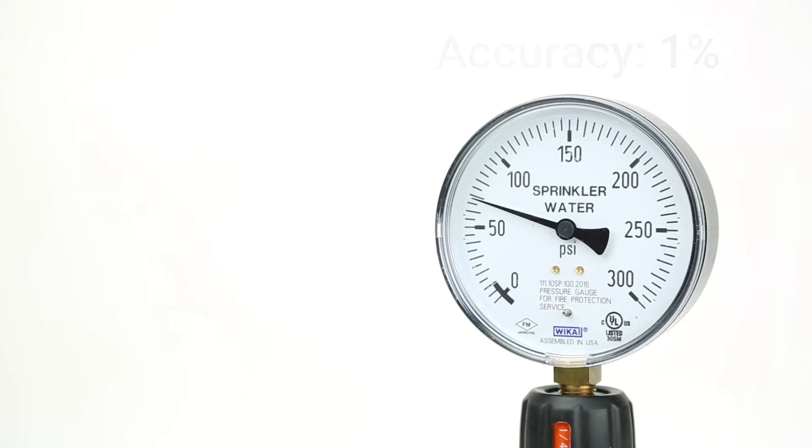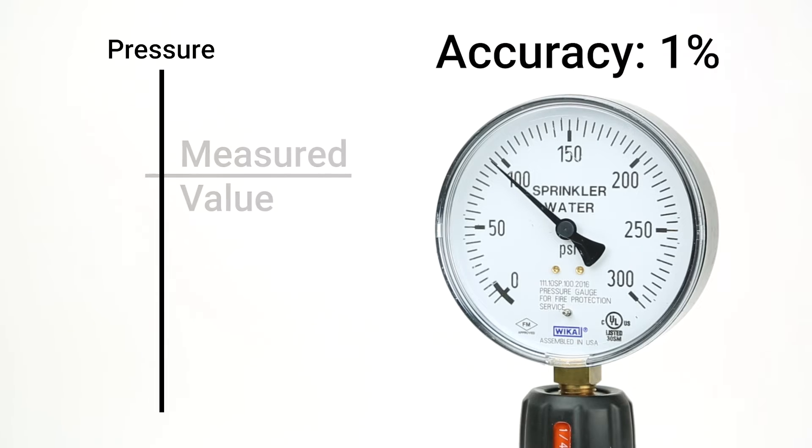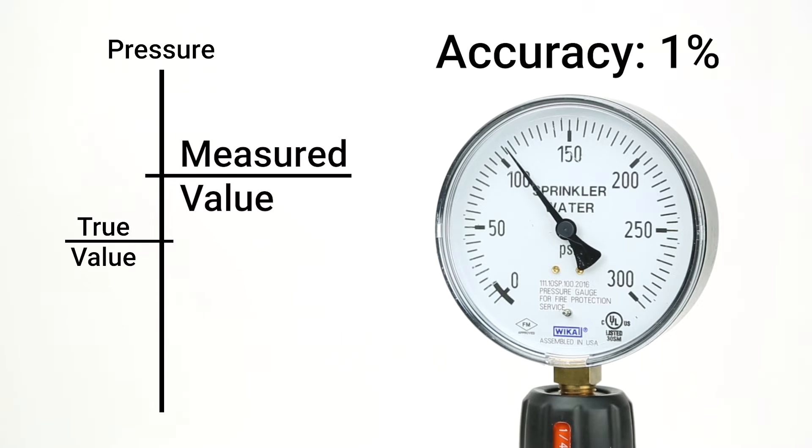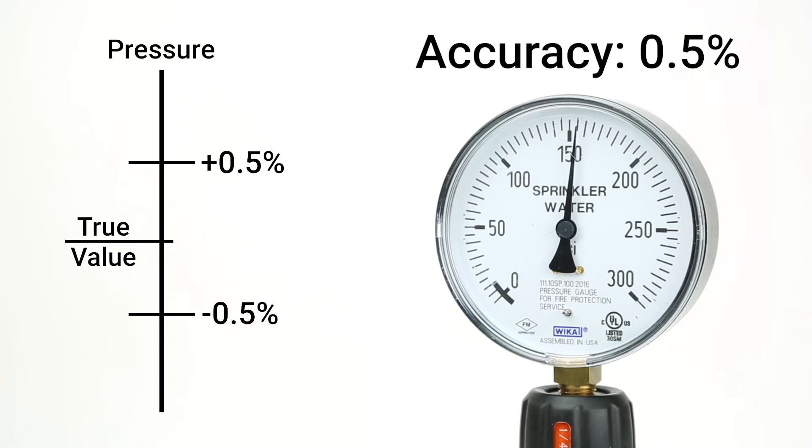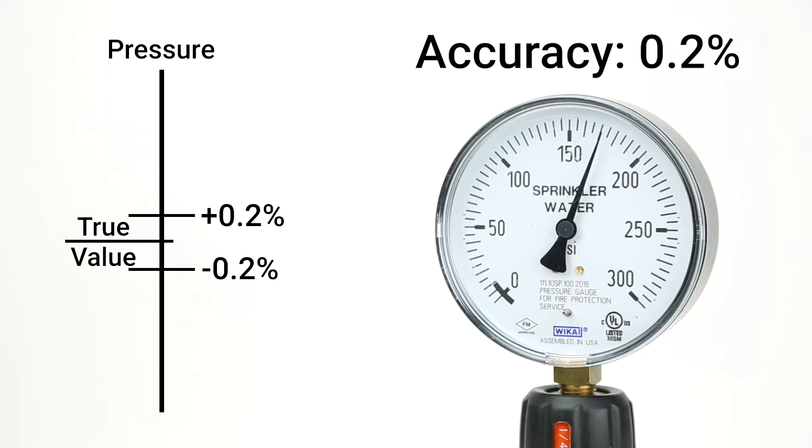When a device's accuracy is stated within its specifications, it represents the maximum difference between the measured value and the true value. A device with an accuracy of 1% is guaranteed to give a reading within 1% of the true value. This means that lower accuracy values are actually more accurate because they have a smaller range around the true value.